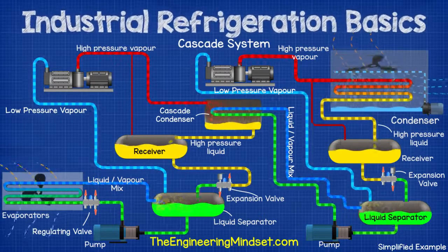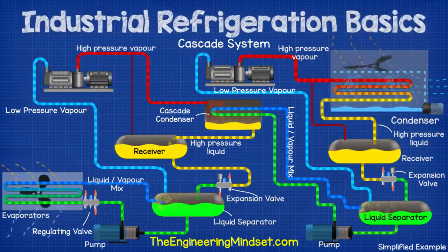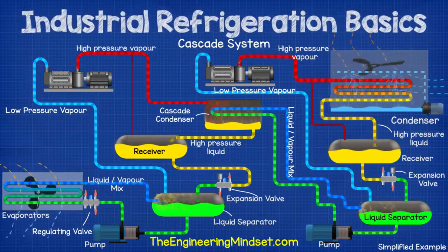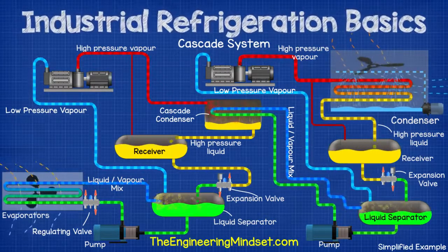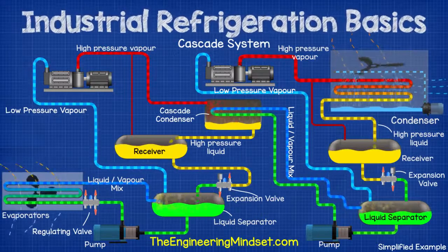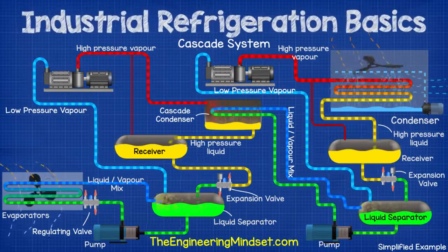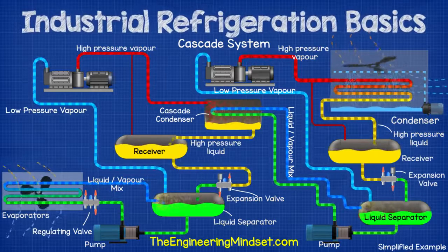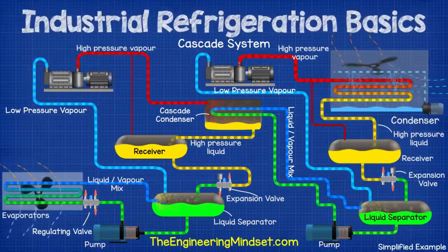The two refrigerants can be the same or they can be different and optimized for each circuit. For example, we could use ammonia for the high temperature side and CO2 for the low temperature side. This would mean that less ammonia is used and the system would be more efficient compared to a two-stage ammonia-only system.